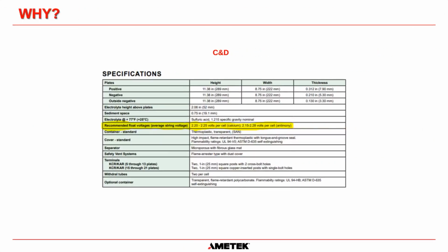So for C and D, you can see that the recommended float voltage for this particular type of cell is between 2.2 and 2.25 for calcium cells. So you would set it at 2.23 for a calcium cell. And if it's an antimony cell, C and D is saying it should be between 2.15 and 2.28. And that's a 13 difference. So it would be about 2.21 volts per cell. Okay. So that's C and D.